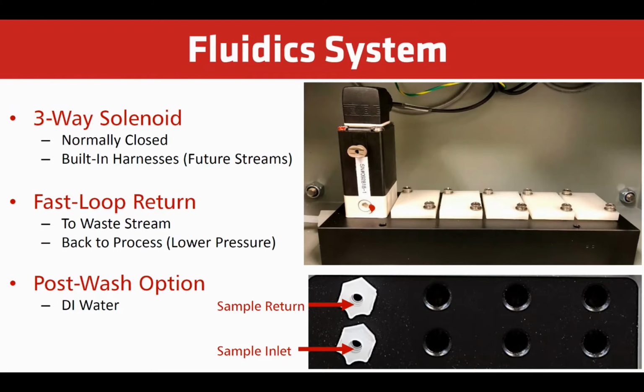We also offer, for cleanup after analysis, a post-wash option with DI water, either through a pressurized source, where we would have another sample valve that we would use and plumb DI water to, or use a peristaltic pump and pump it from a reagent container underneath the analyzer.